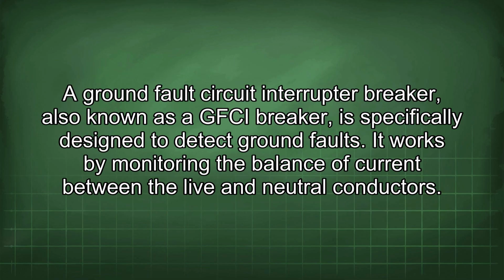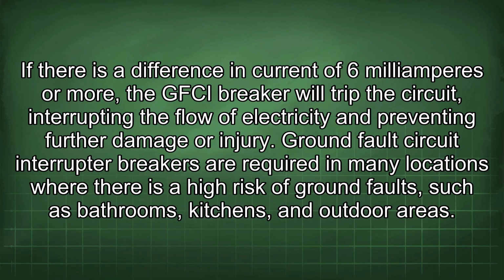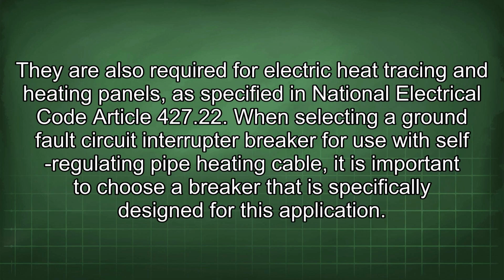A ground fault circuit interrupter breaker, also known as a GFCI breaker, is specifically designed to detect ground faults. It works by monitoring the balance of current between the live and neutral conductors. If there is a difference in current of 6 mA or more, the GFCI breaker will trip the circuit, interrupting the flow of electricity and preventing further damage or injury. Ground fault circuit interrupter breakers are required in many locations where there is a high risk of ground faults, such as bathrooms, kitchens, and outdoor areas. They are also required for electric heat tracing and heating panels, as specified in National Electrical Code Article 427.22.